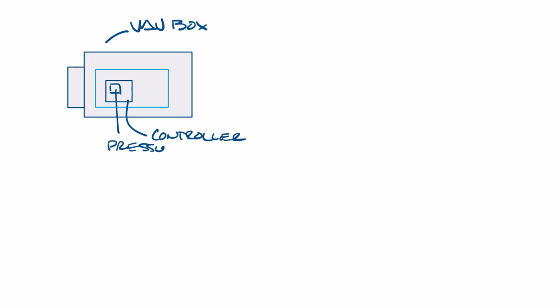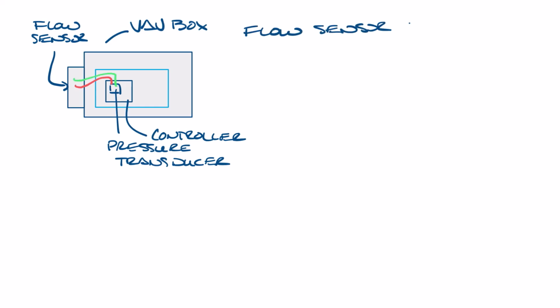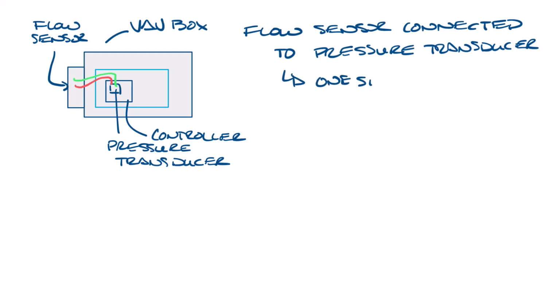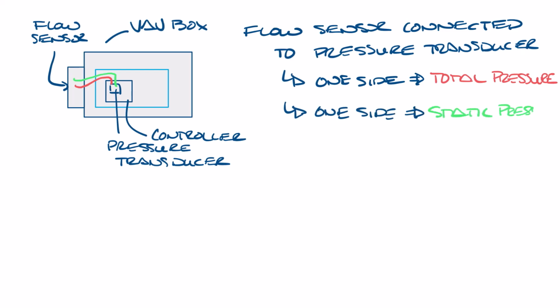So let's move this over and look at this. So let's draw a VAV box, and this is its inlet, a control enclosure with a controller inside, and this is the pressure transducer. Now you'll have a flow sensor in this inlet, and coming from that flow sensor will be 2 tubes connected to the pressure transducer on the controller. One side of the pressure transducer is connected to the total pressure side of the airflow sensor, and the other side is connected to the static pressure side.